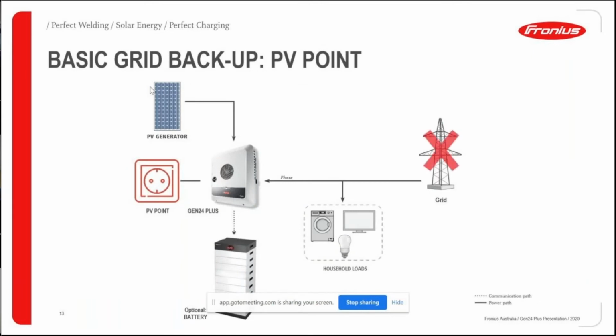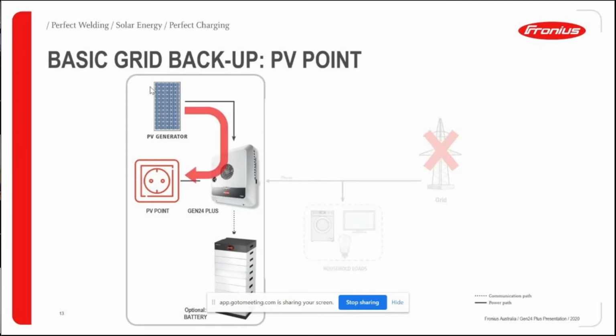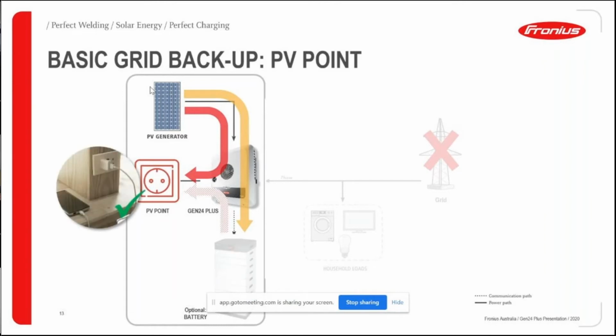It will also work if you do have a battery as well. So if the grid goes down, this just shows how it works. You're getting power straight through from your PV array to PV point when the grid is down. And if the customer has a battery, it will also be able to supply power to PV point, and you can also charge the battery at the same time from the solar. So you've got the option of giving people some basic backup power without even having to add a battery.